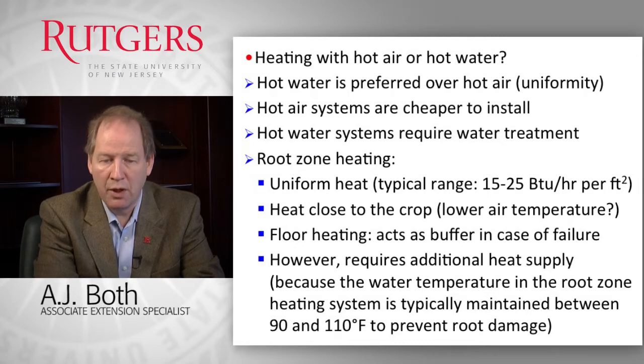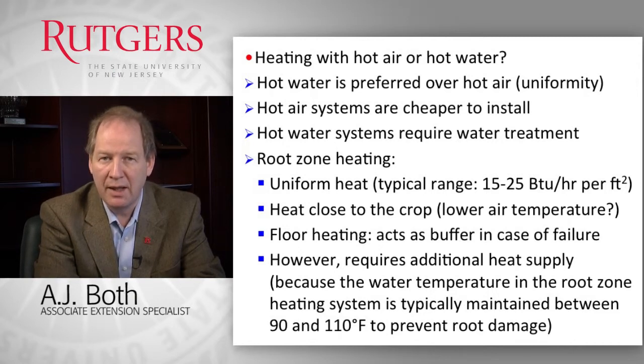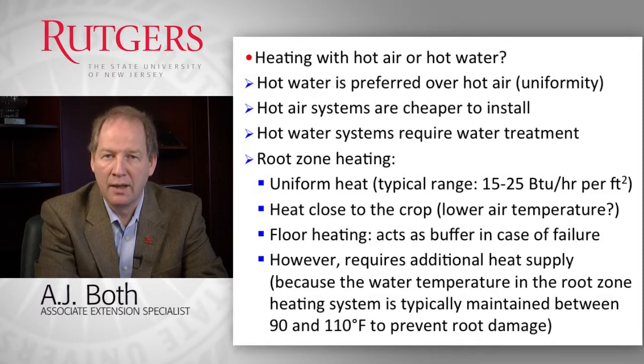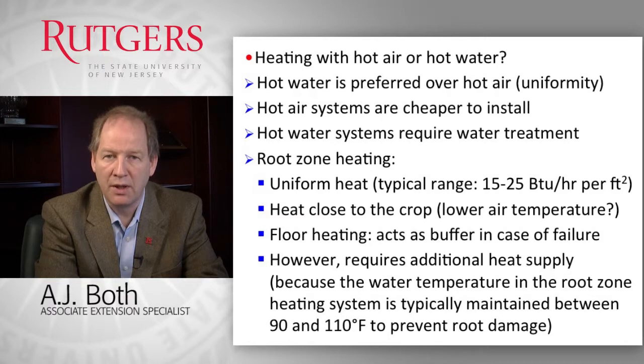One question most growers ask is which is better — a hot air or hot water system? I recommend hot water systems because of the increased uniformity of heat distribution. However, hot air systems are typically cheaper to install, which can be a major consideration. Hot water systems also often require water treatment because dissimilar metals in the system can cause corrosion and premature failure if the water is not treated properly.